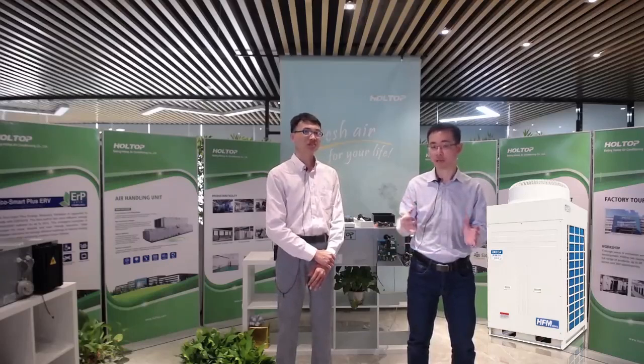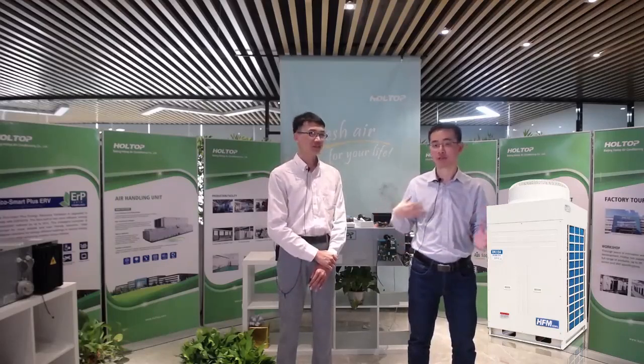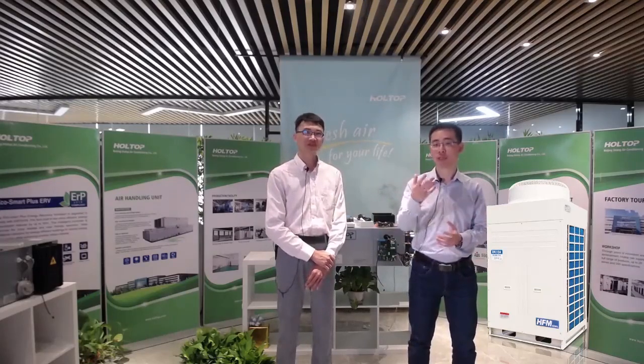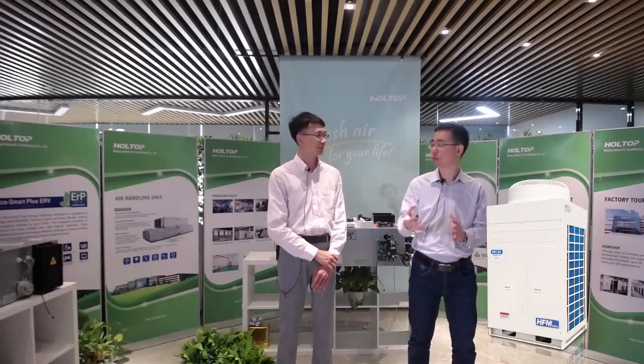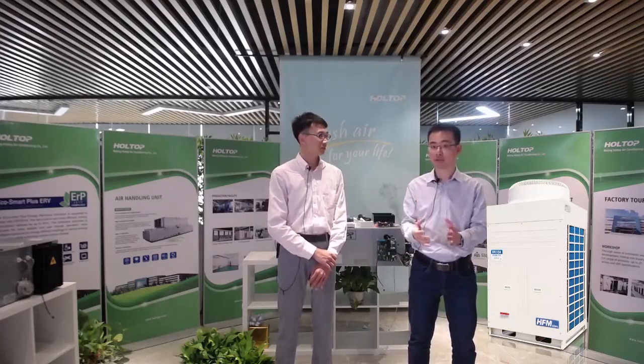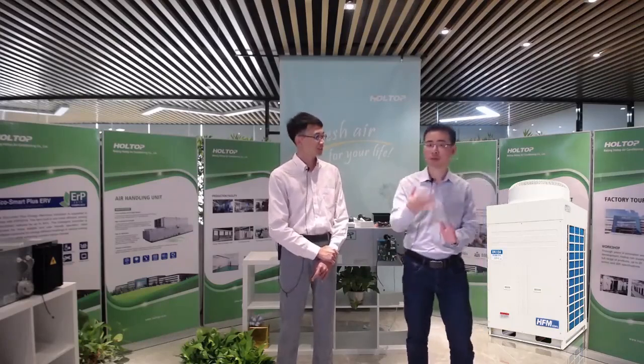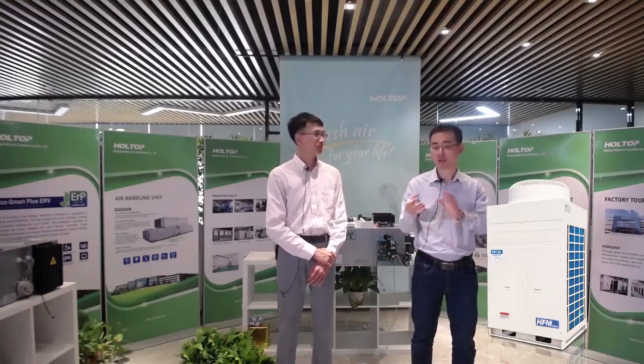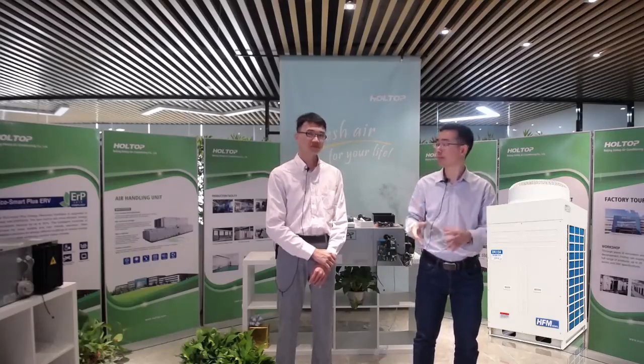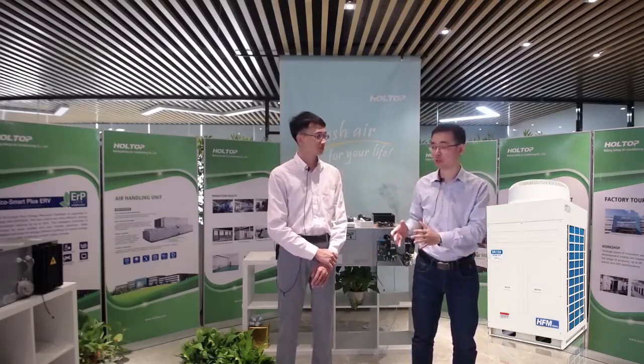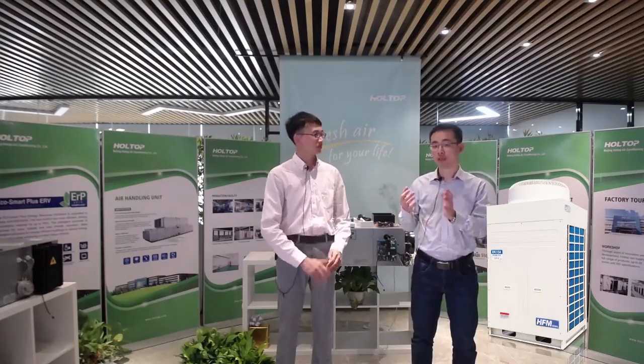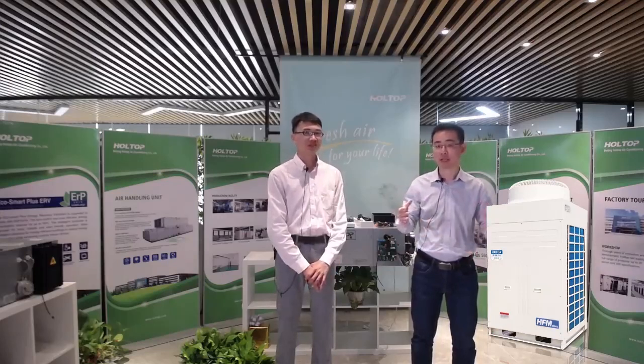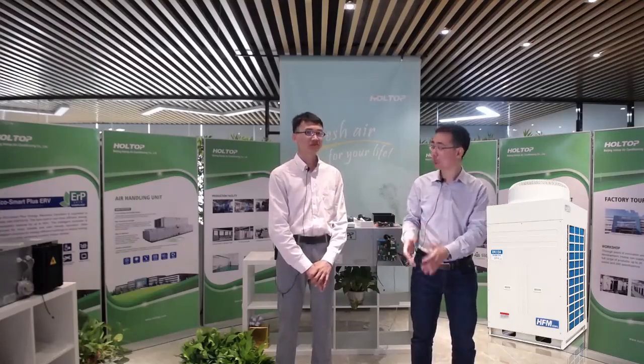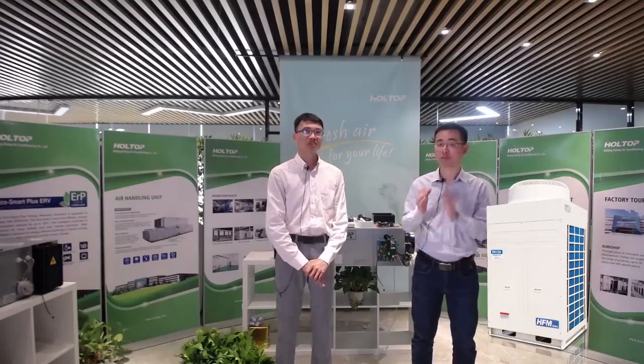The air-to-air heat recovery AHU with DX coil would be a very good idea for most spaces. For example, for industrial use, such as a factory manufacturing goods, which has very high requirements for indoor air temperature and cleanness. Normally people will introduce fresh air from outside, cool it with the air conditioner and then send it indoors. But in this case, a lot of exhaust air would be just sucked out directly to the outdoors, and a lot of energy consumption of the indoor air conditioner would be wasted. So we can use this air-to-air heat recovery AHU to recover the indoor cool air from the exhaust to pre-cool the fresh air.